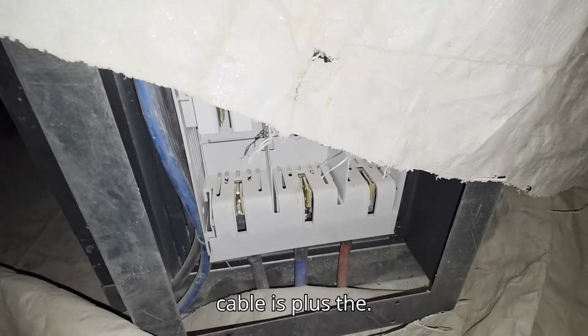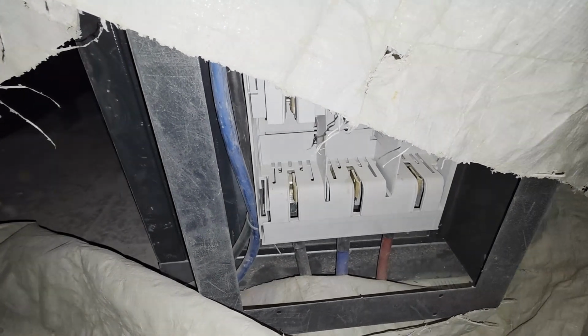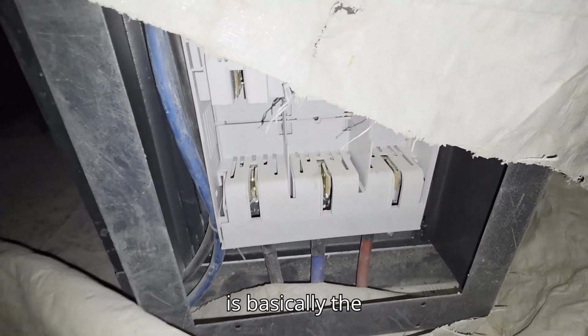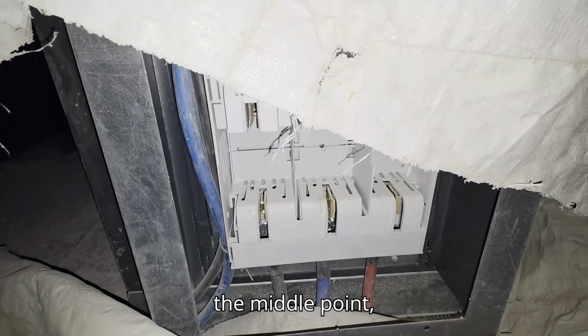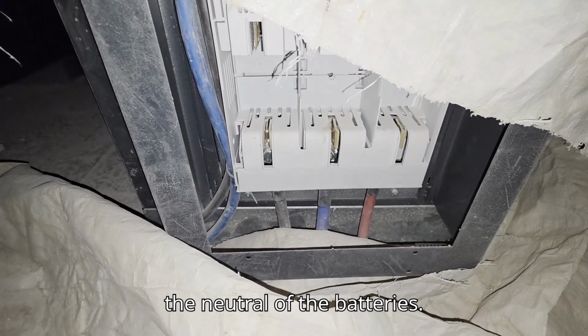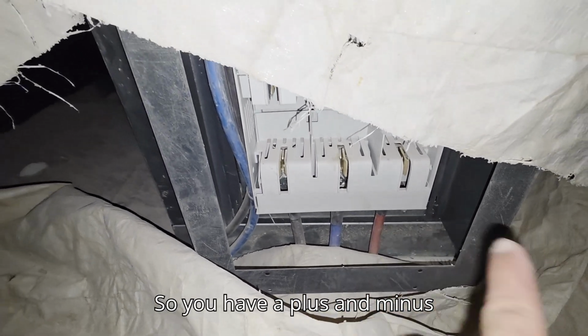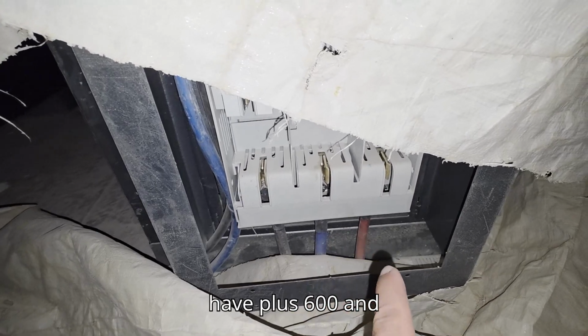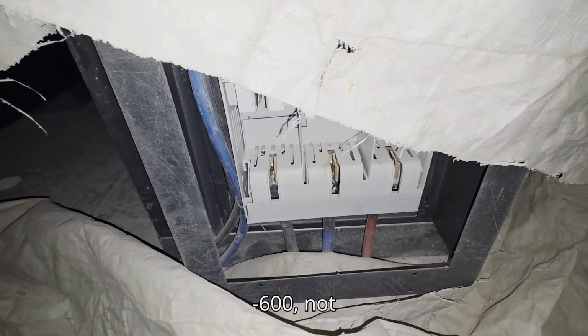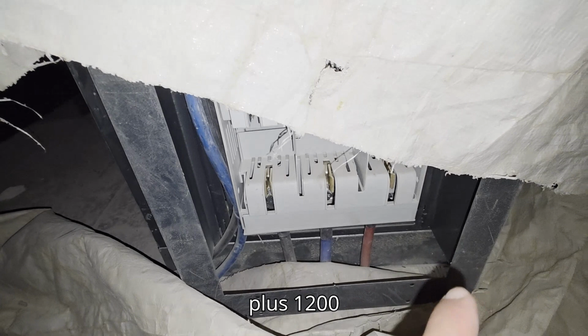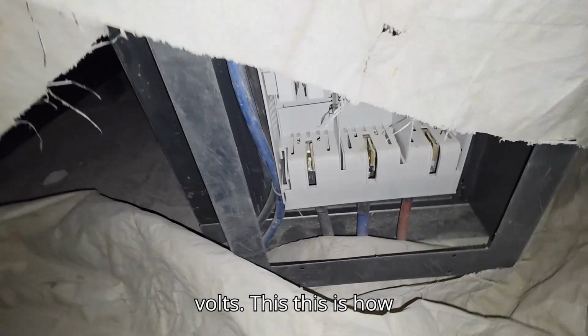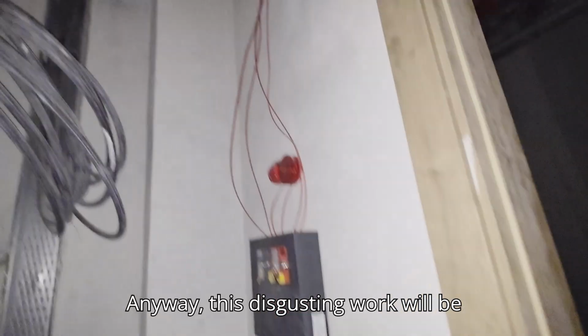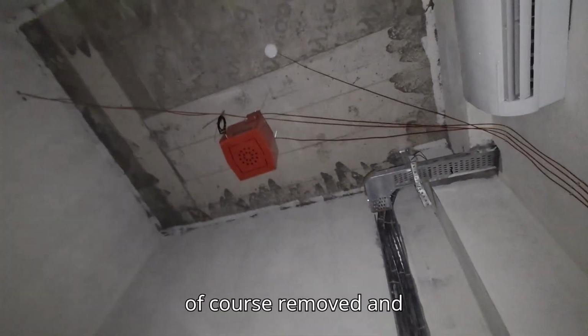The red cable is plus, the black cable is minus, and the blue cable is basically the middle point, the neutral of the batteries. So you have a plus and minus. You have a plus 600 and minus 600, not plus 1200 volts. This is how big UPSs work. Anyway, this disgusting work will be, of course, removed and modified.